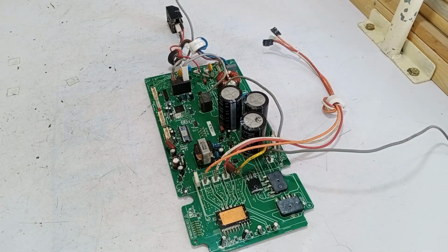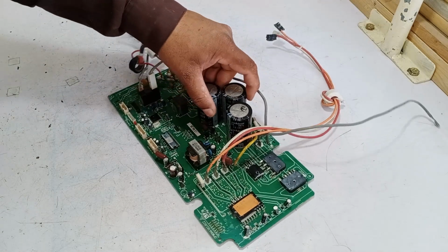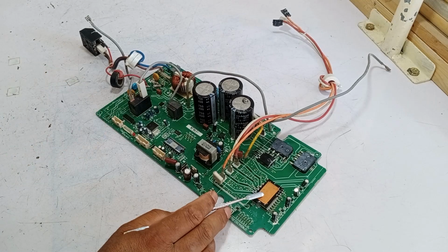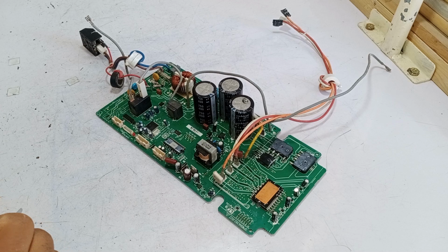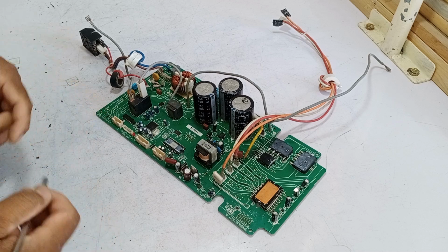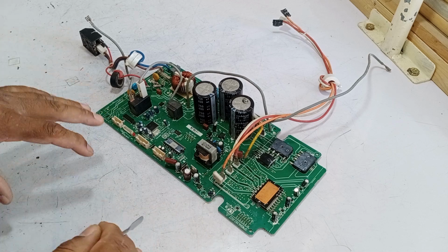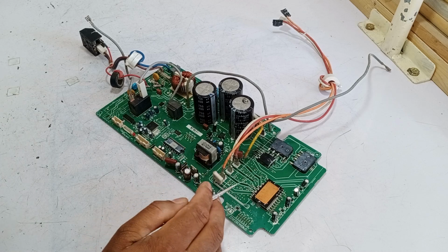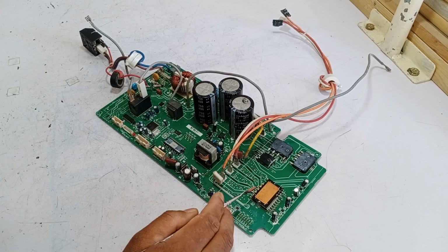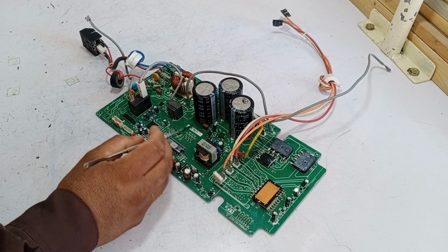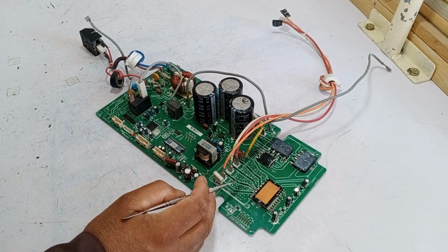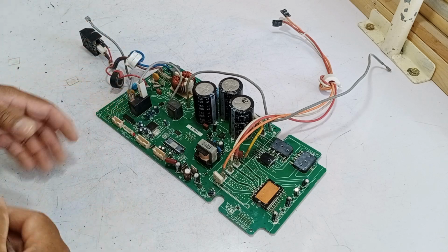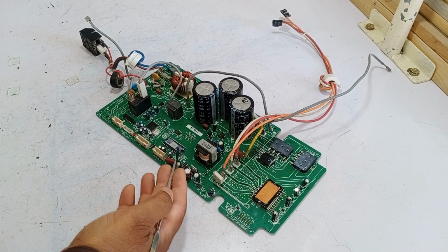Now, if we talk about the PCB, it can also cause this issue if it's faulty. 1. IPM short circuit. If the IPM gets short-circuited and heavily damaged, the entire PCB stops functioning, which might lead to a different error code. However, in some cases, the IPM might be short-circuited, but the PCB fails to detect it. When the PCB tries to drive the IPM in this state, the IPM won't work, and the compressor will also fail to start. This results in the abnormal compressor rotation error.